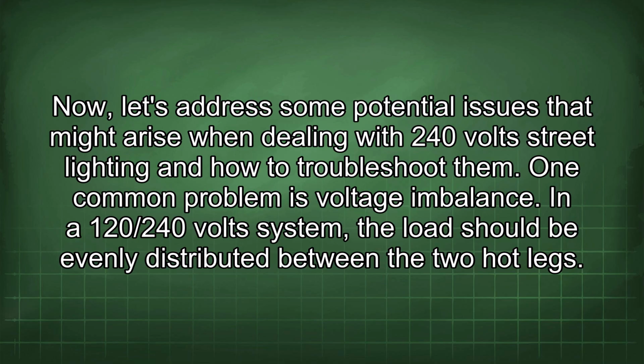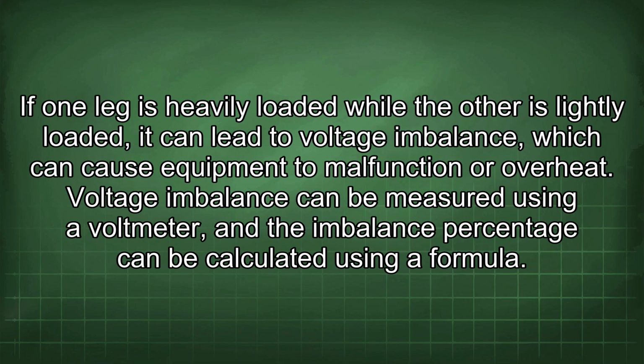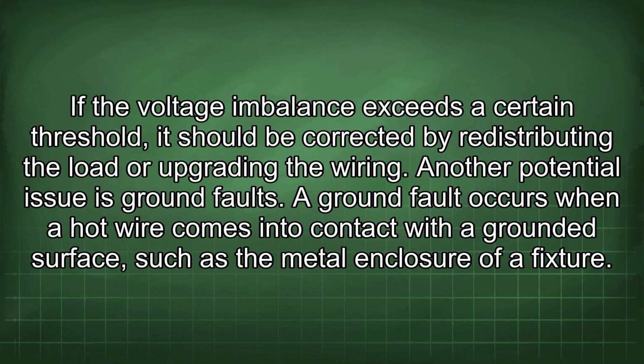Now, let's address some potential issues that might arise when dealing with 240 volt street lighting and how to troubleshoot them. One common problem is voltage imbalance. In a 120/240 volt system, the load should be evenly distributed between the two hot legs. If one leg is heavily loaded while the other is lightly loaded, it can lead to voltage imbalance, which can cause equipment to malfunction or overheat. Voltage imbalance can be measured using a voltmeter, and the imbalance percentage can be calculated using a formula. If the voltage imbalance exceeds a certain threshold, it should be corrected by redistributing the load or upgrading the wiring.